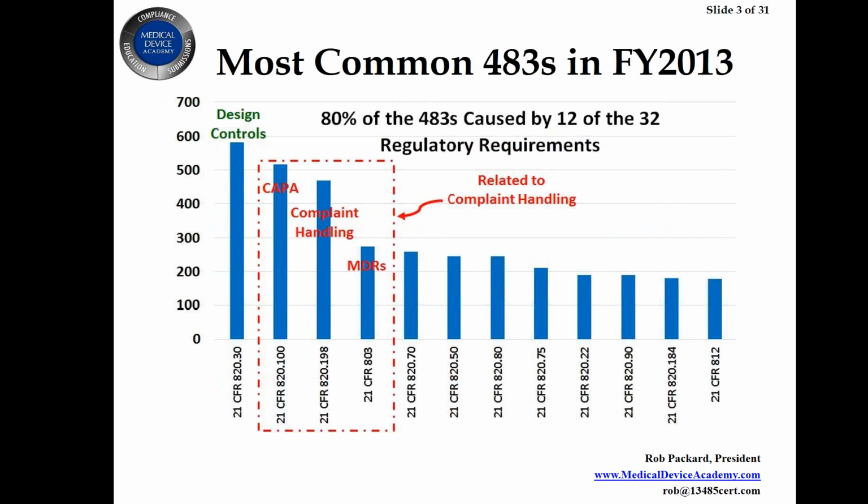The first thing I like to cover whenever I'm covering regulations is to explain why it's important. And usually what that comes down to is, what will the FDA do to me, particularly when it's an FDA regulation? And so the FDA comes through and does routine inspections. They have both level 1 inspections and level 2 inspections. And the level 1 inspections are abbreviated and they don't always cover design controls, but the level 2 inspections, design controls is one of the areas they cover every single time.